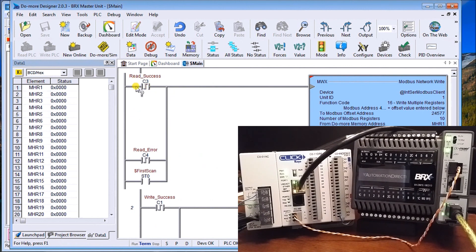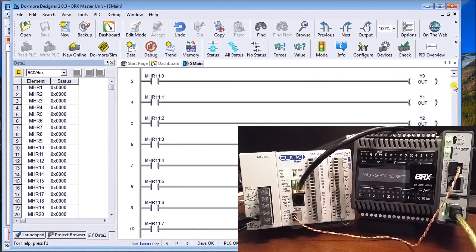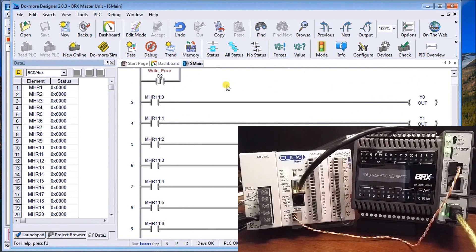In the program logic: a read success from the read instruction triggers the write to fire and go out to the network. We also have a first scan, so as soon as the controller goes into run mode it will automatically trigger a write to the network. After a write success or write error, it then reads back the information. This is how the timing works — it cycles very quickly back and forth. The outputs are also mapped so that MHR11, read from the Click, will turn on output Y0 if bit zero is set.